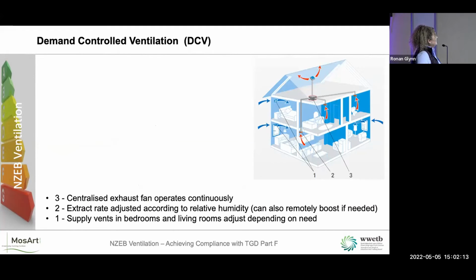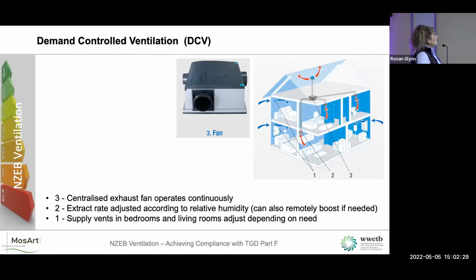Demand control ventilation, which Gary mentioned, I'll just briefly go through. It's very like CMEV, so it has a constant extract demand, then it ramps down below the general ventilation rate when the demand is not there. When the demand is there, the fan clicks in and extracts from the exhaust units, these red ones here, back into the centralized fan, again to the outside. The difference is that instead of normal background ventilators, there's a little restrictor on the ventilator, on a humidity sensitive strip. As the humidity increases in the room, the background ventilators open up and let some air in.